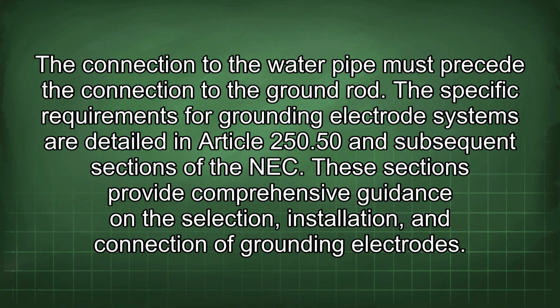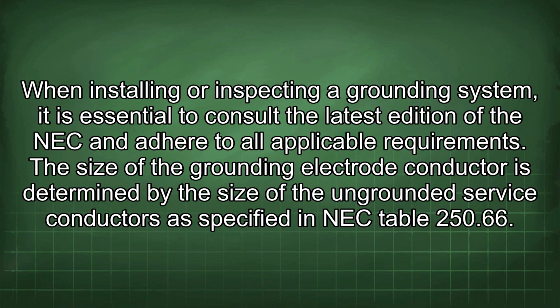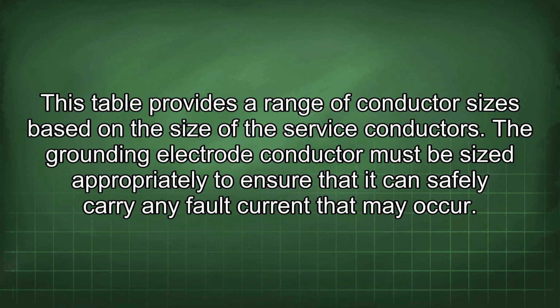The specific requirements for grounding electrode systems are detailed in Article 250.50 and subsequent sections of the NEC. These sections provide comprehensive guidance on the selection, installation, and connection of grounding electrodes. When installing or inspecting a grounding system, it is essential to consult the latest edition of the NEC and adhere to all applicable requirements. The size of the grounding electrode conductor is determined by the size of the ungrounded service conductors as specified in NEC Table 250.66. This table provides a range of conductor sizes based on the size of the service conductors.